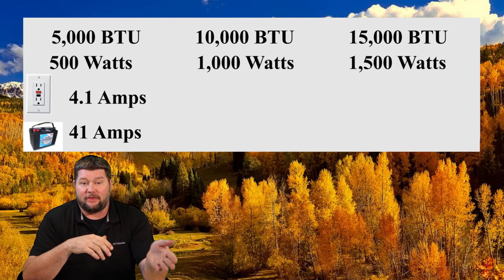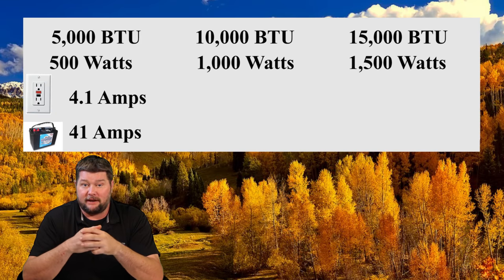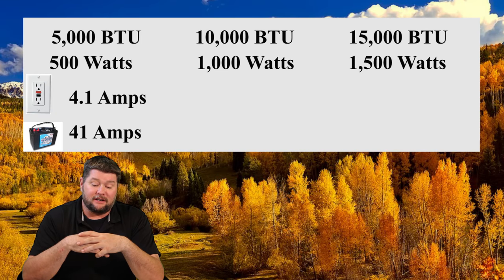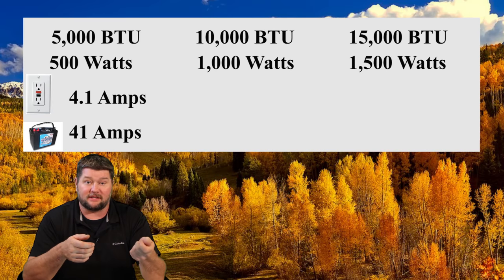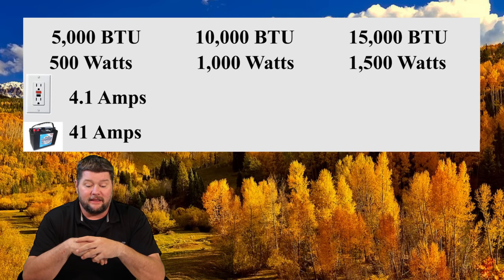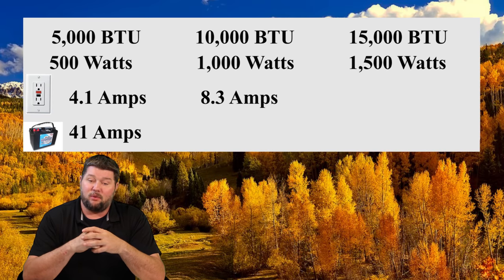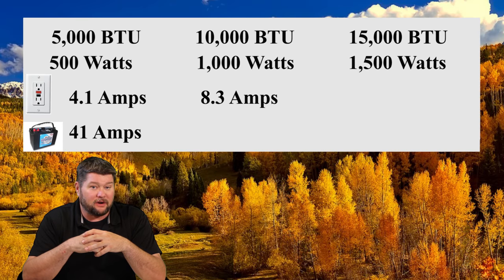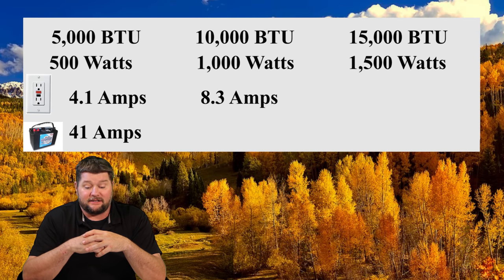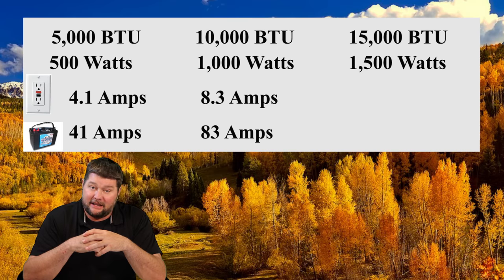As far as the 1,000-watt window unit, that's going to use — if you're plugged in at home with 120 volts at your wall socket — 8.3 amps. If you're trying to run that off battery power and you're using a 12-volt system, that's going to cost you a whopping 83 amps of power.